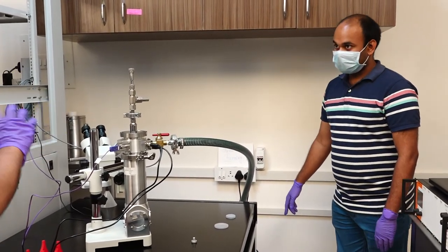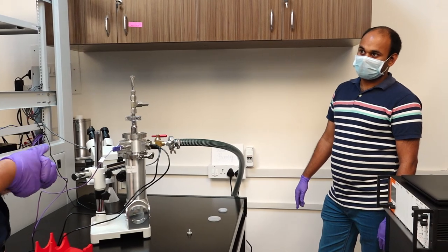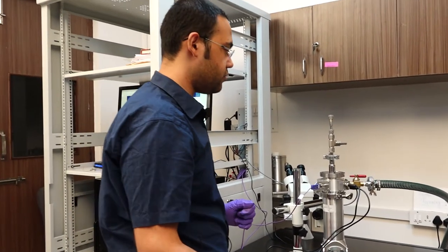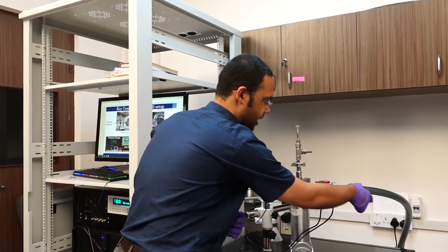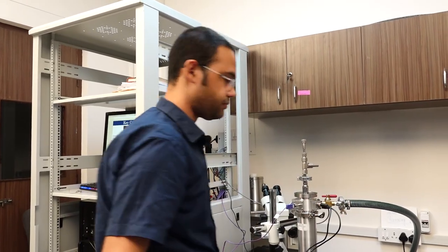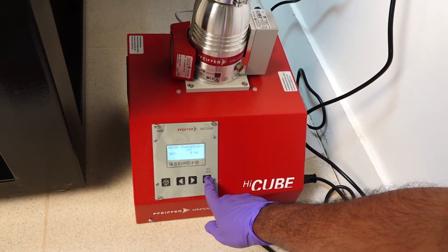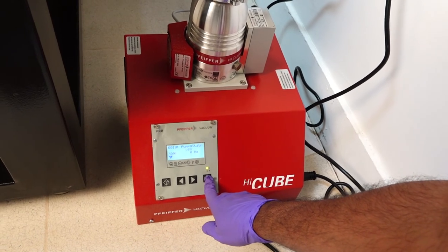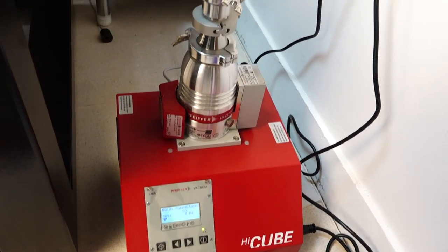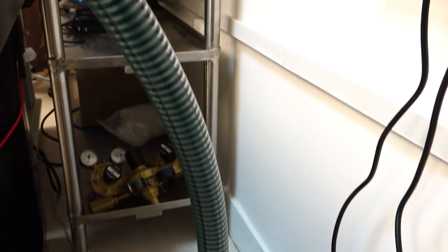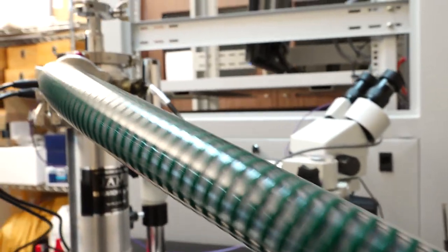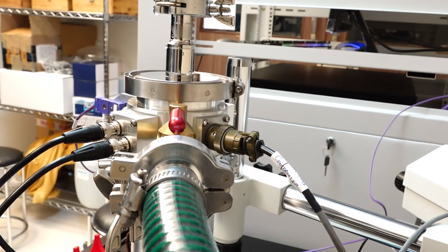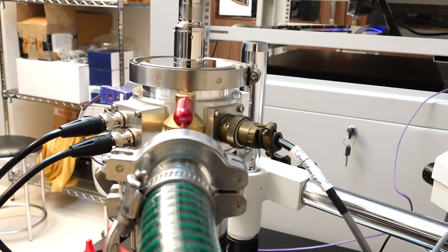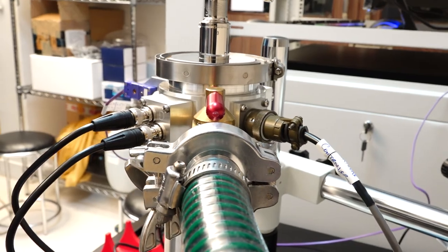And once we get a good contact to the device, we will start going down to low pressures using, as shown, the pipes we had connected to the turbo pump. We'll now switch on the turbo pump, as can be seen here. We turn on the turbo pump by pressing that button, which turns on both the roughing and the turbo pump. And we continue this until the desired pressure is reached.